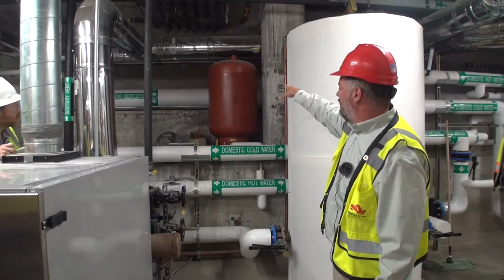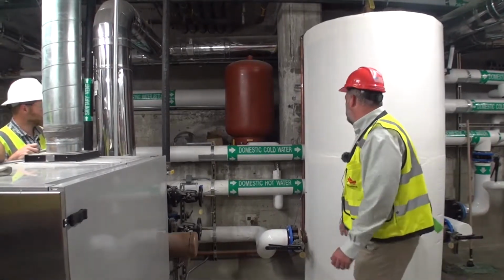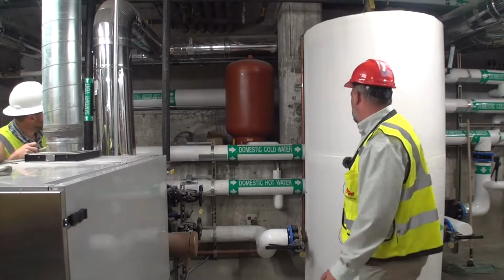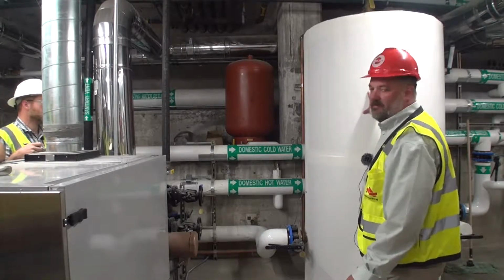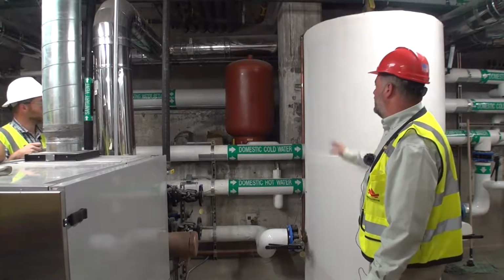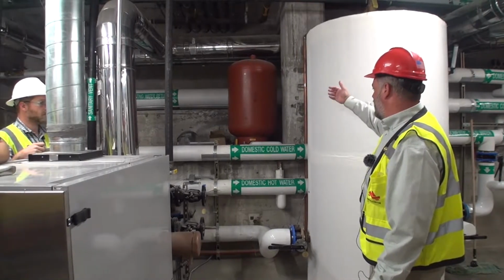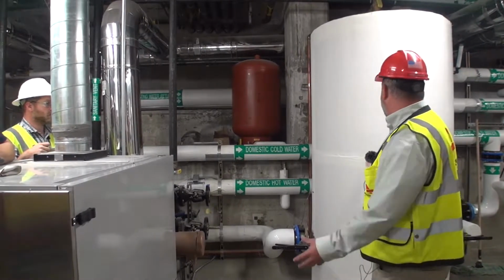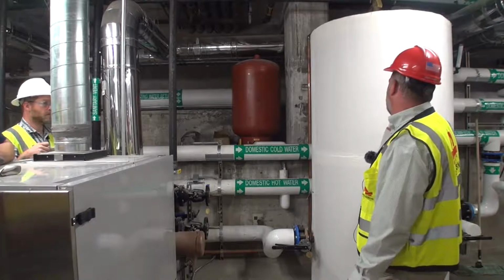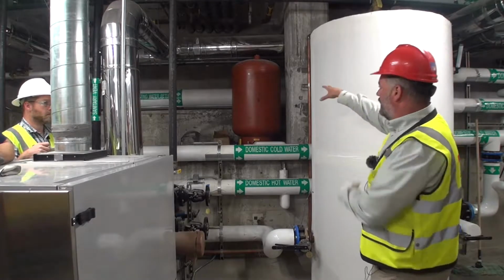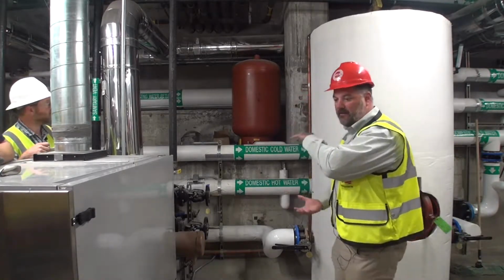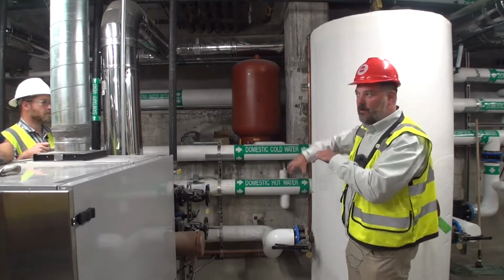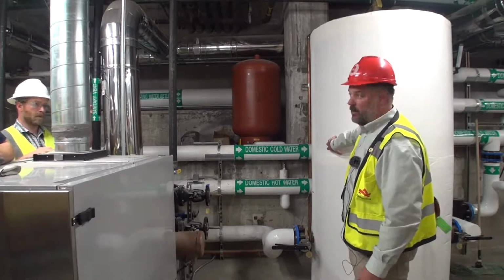That's our expansion tank right here on the system. That expansion tank is covering the load of thermal expansion off the tank and off the line. Again, that tank is pressurized to a point that's a balance, so that when thermal expansion is happening on the storage tank, it's going to route back and go into that tank. There's a bladder in that tank that's going to take that impact, so we're not taking it on our storage tank. Yes, sir.